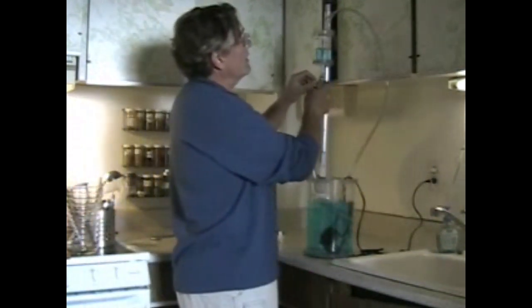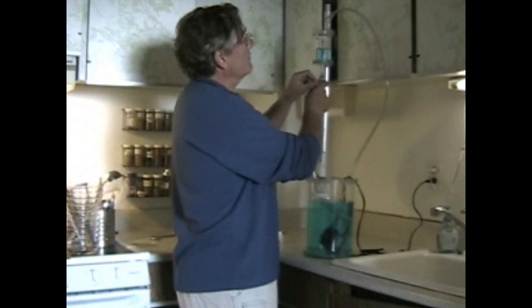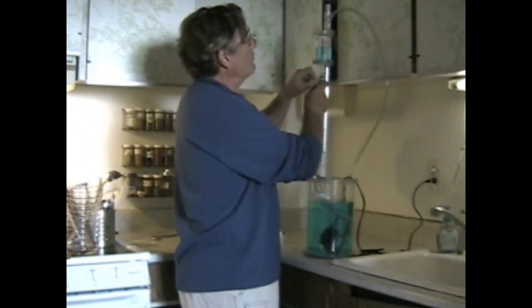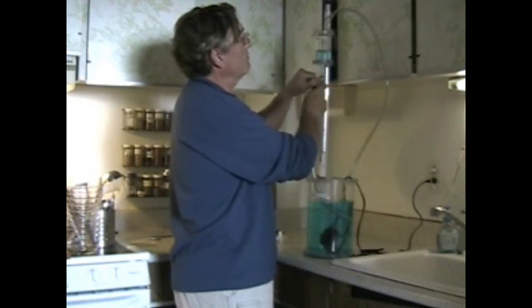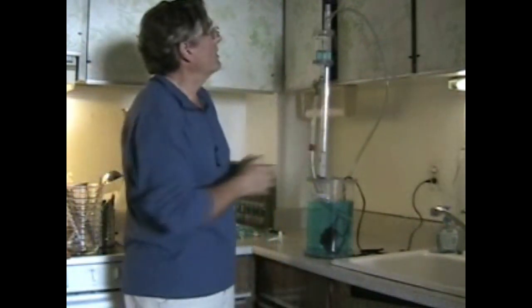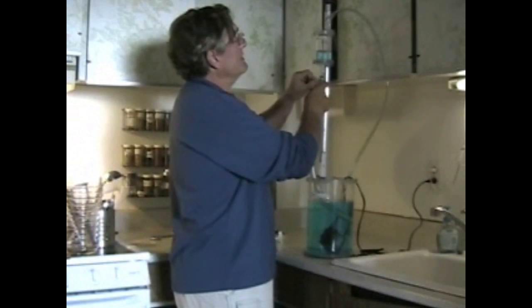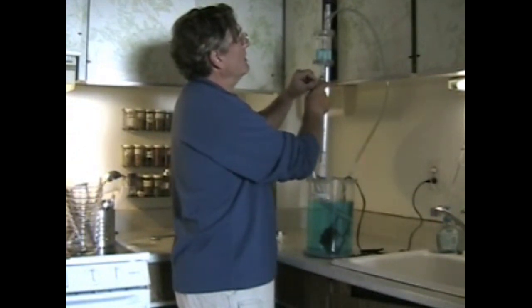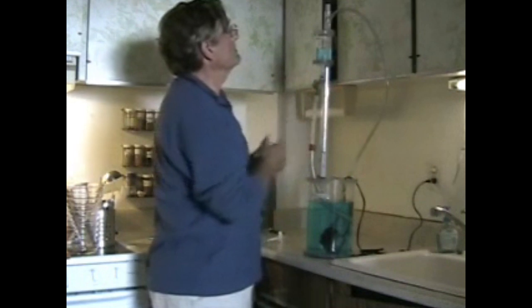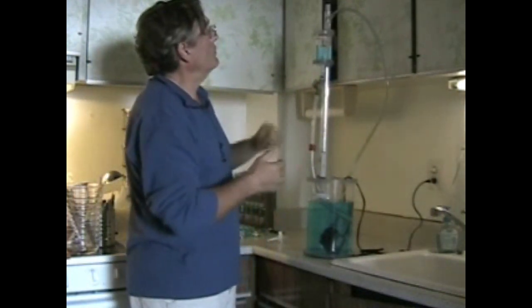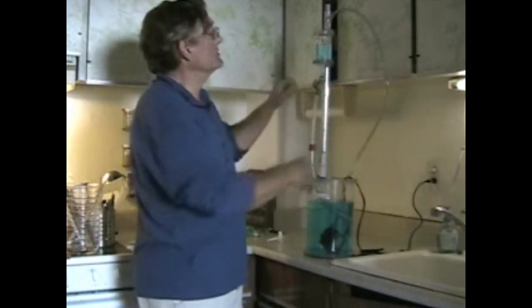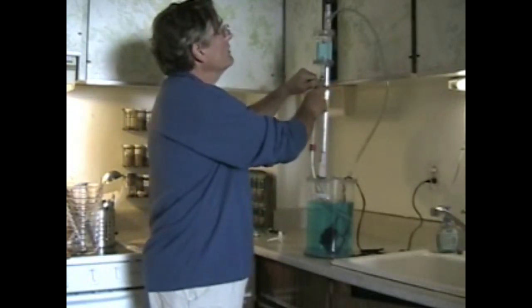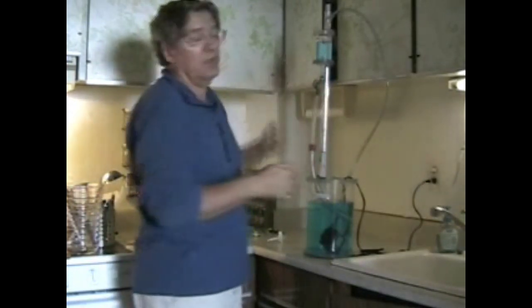And if I increase the flow rate in such a way to make the level drop, we'll get a vortex formation just about immediately, as you can hear from the noise. If I get the level to increase again, I can get the vortex to disappear. So the vortex is dependent on the submergence height between the tank surface and the intake.